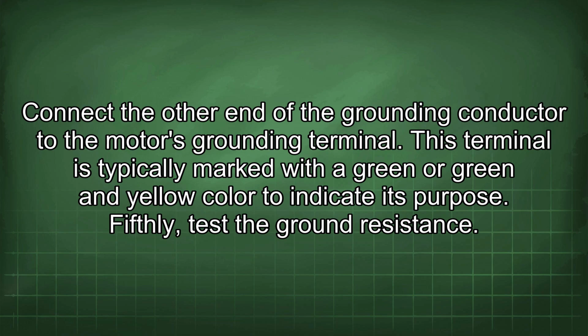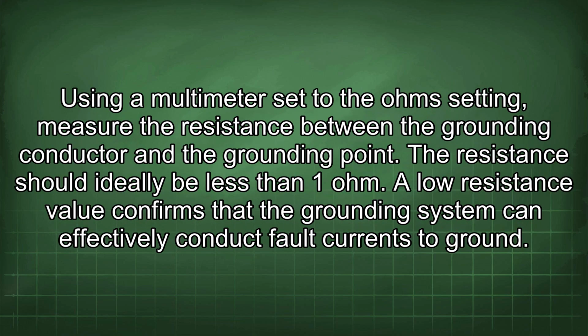Fifthly, test the ground resistance. Using a multimeter set to the ohms setting, measure the resistance between the grounding conductor and the grounding point. The resistance should ideally be less than 1 ohm. A low resistance value confirms that the grounding system can effectively conduct fault currents to ground.